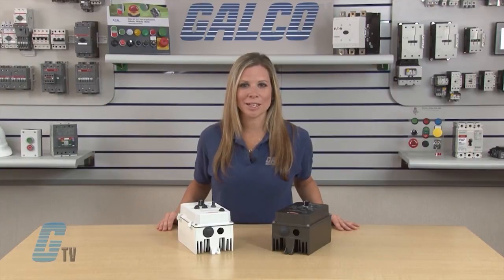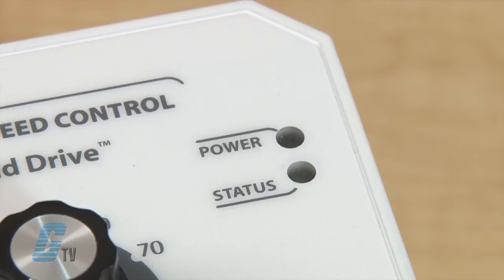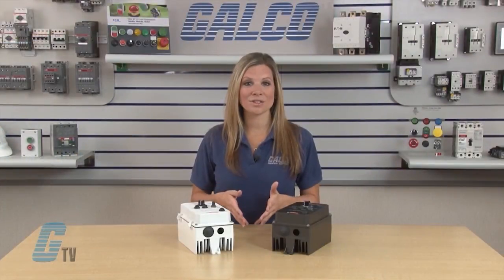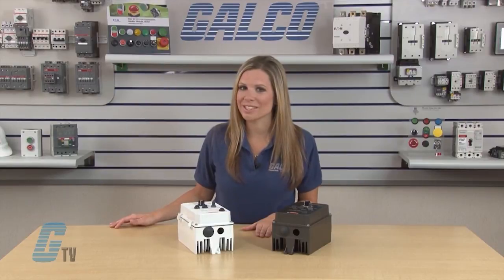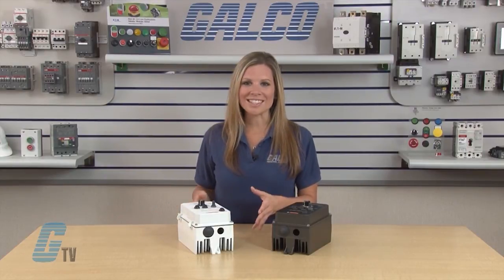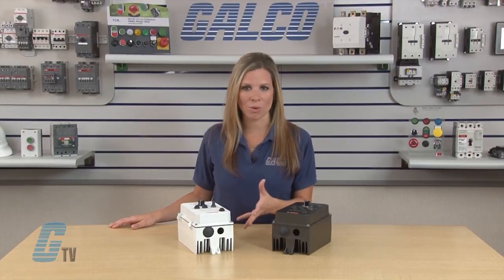They feature 200% starting torque and diagnostic LED status indicators. The KBAC has sensorless flux vector control. The flux vector compensation with static auto-tune provides excellent speed regulation with high torque loads throughout the entire speed range.